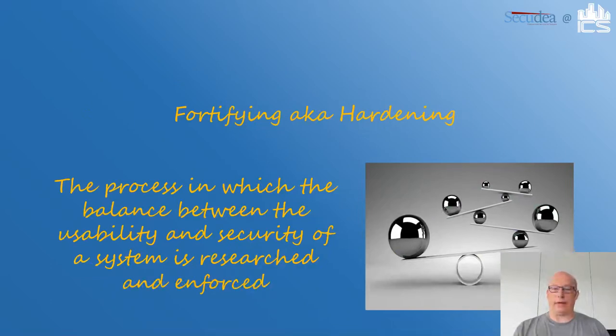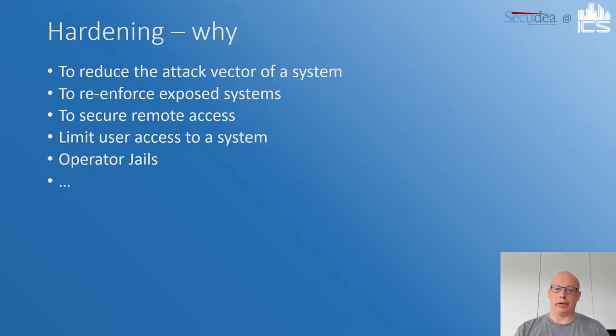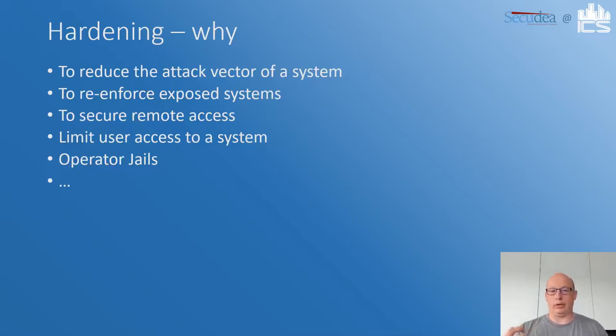Now a little bit more about fortifying ICS systems. Hardening is actually the process in which the balance between usability and security of a system is researched and enforced. Why would you think of doing hardening on ICS systems? The more systems are interconnected, the more there are potentially attack vectors. Hardening is the process in which we try to reduce those attack vectors, reinforce exposed systems, secure remote access, limit user access, or make operator jail protections more foolproof so that operators cannot escape from the operator jails.